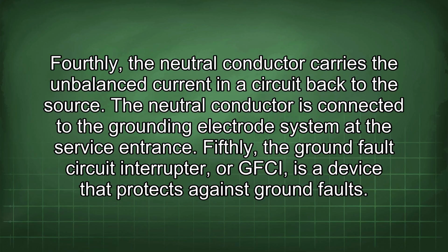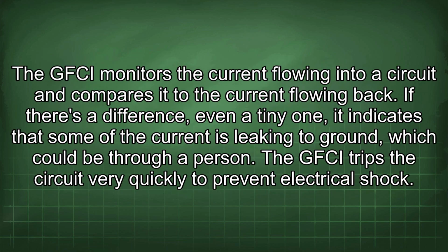Fifthly, the ground fault circuit interrupter, or GFCI, is a device that protects against ground faults. The GFCI monitors the current flowing into a circuit and compares it to the current flowing back. If there is a difference, even a tiny one, it indicates that some of the current is leaking to ground, which could be through a person. The GFCI trips the circuit very quickly to prevent electrical shock.